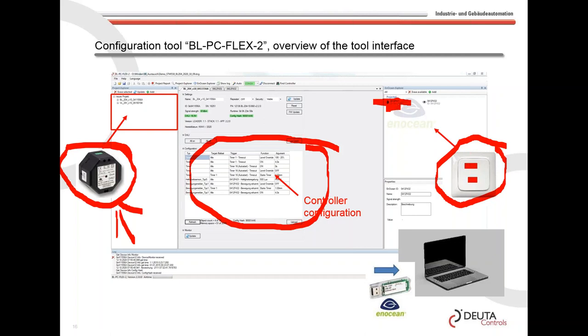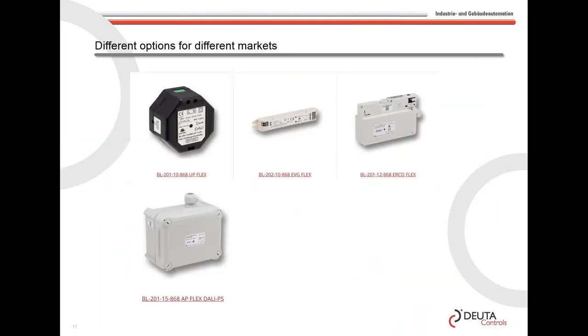You upload the configuration wirelessly to the EnOcean controller — a key difference from other systems on the market. We do not need a wired connection to DALI; everything is done wirelessly. You can enter a customer's building at any time without needing support from an electrician to interface to the DALI lines.